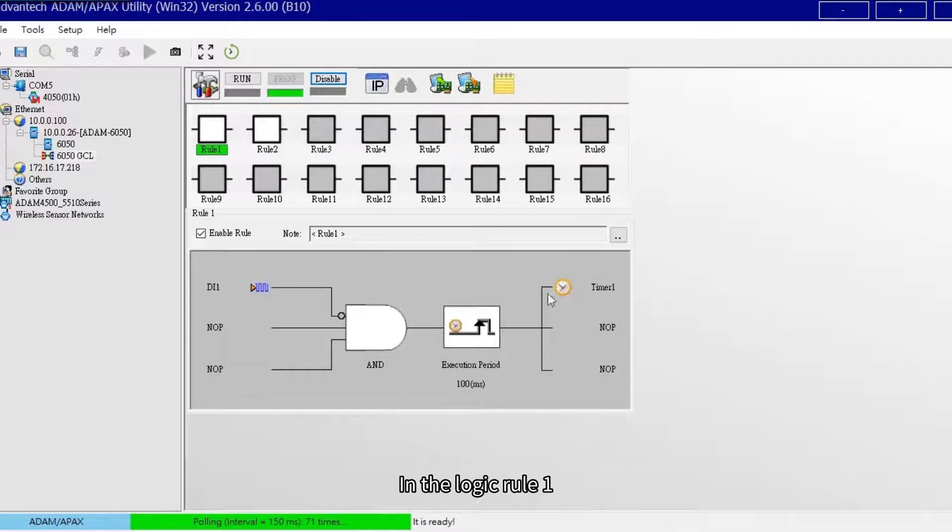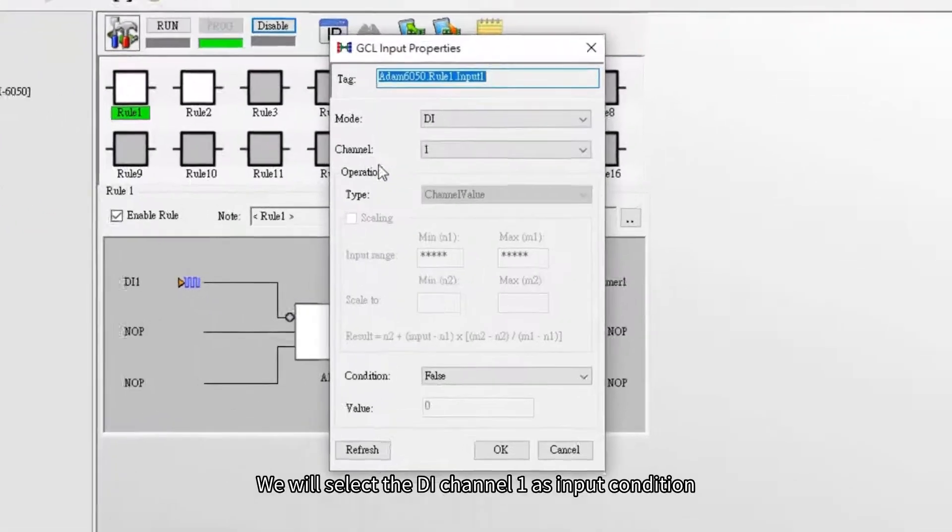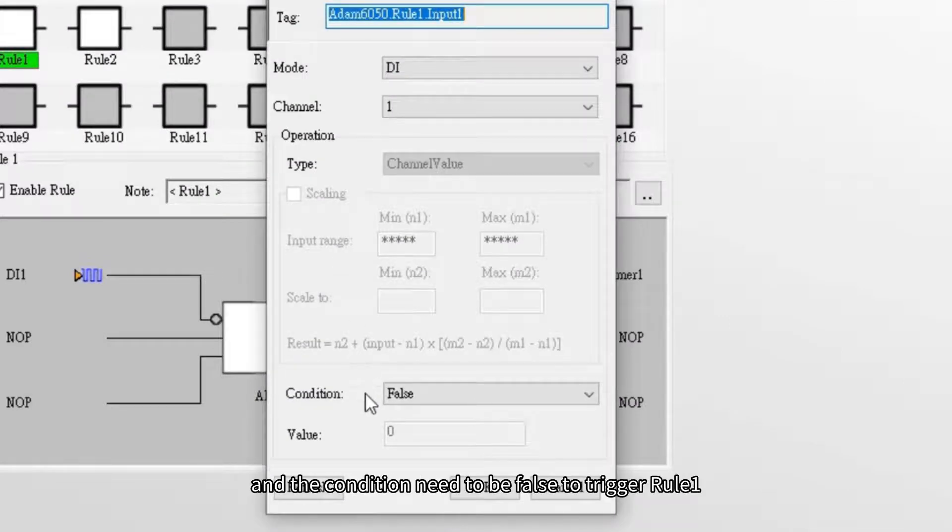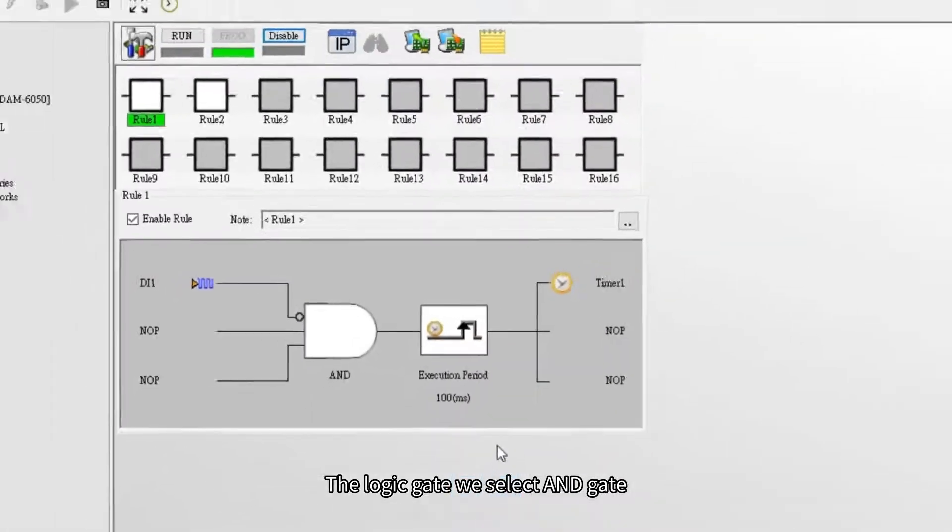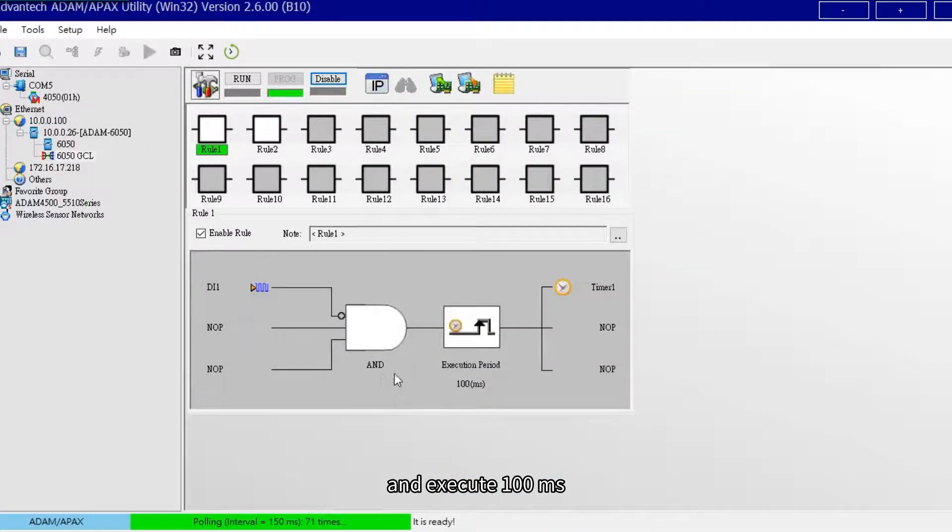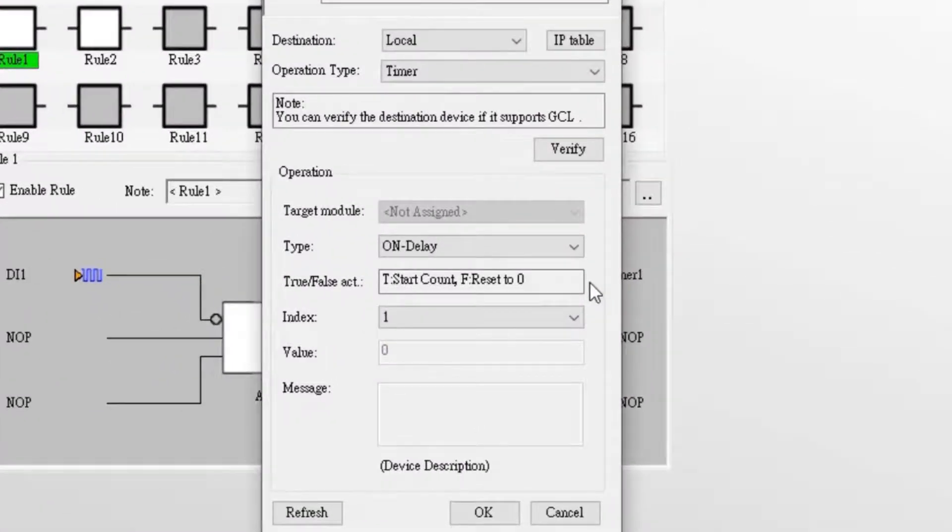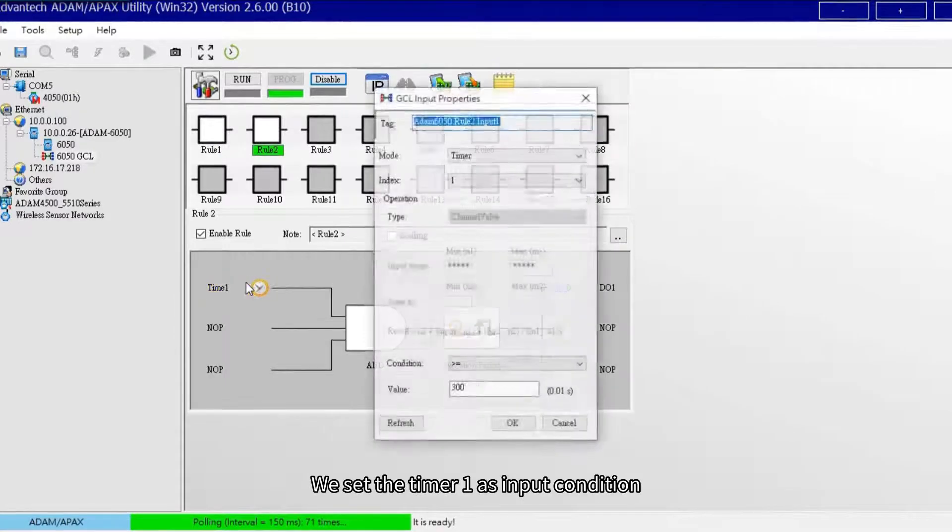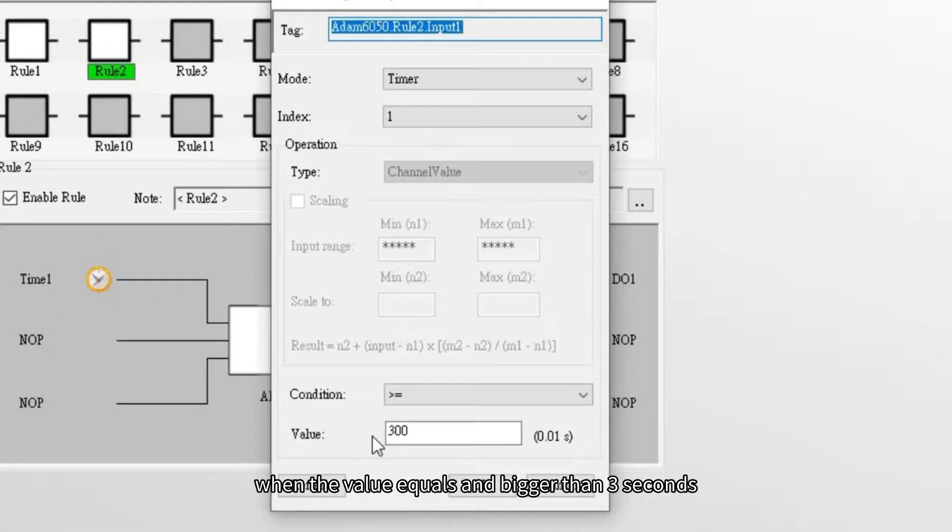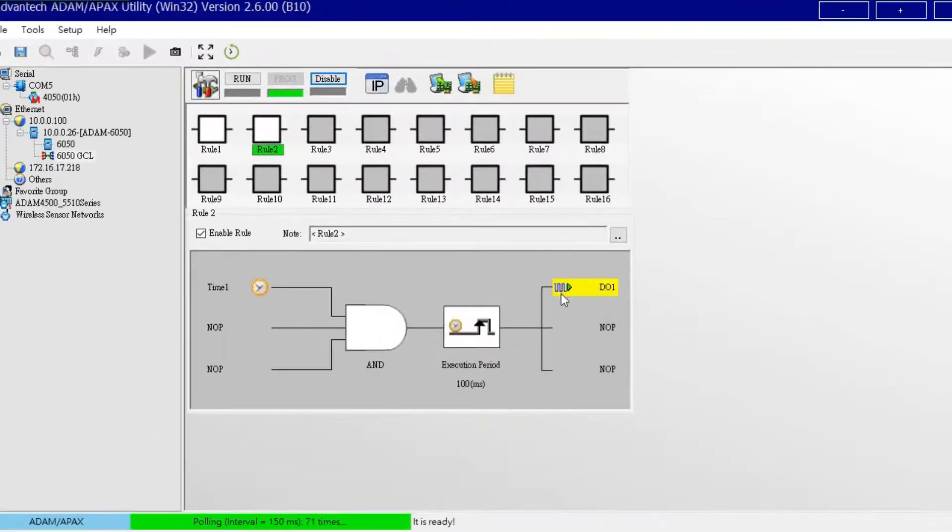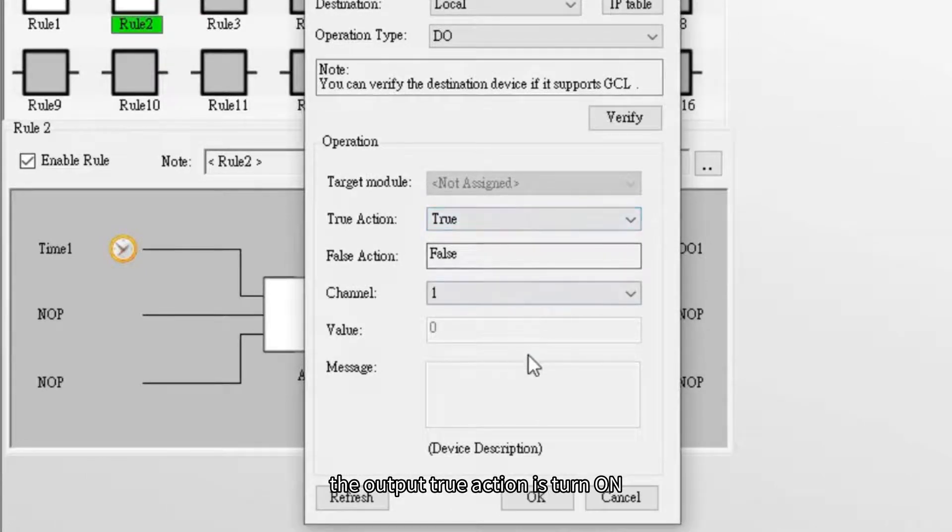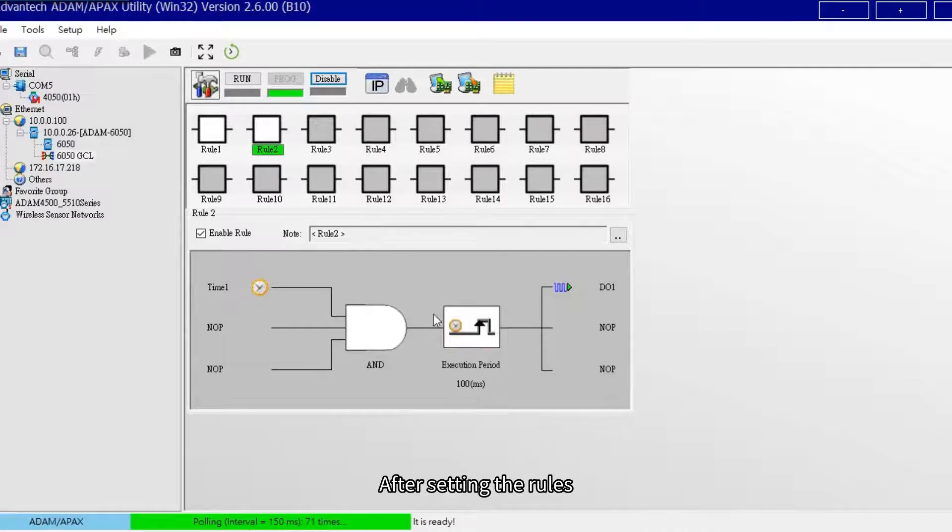In the logic rule 1, we will select the DI channel 1 as input condition, and the condition needs to be false to trigger rule 1. The logic gate, we select AND gate and execute 100 milliseconds, then trigger the timer 1 to do the on delay. In the logic rule 2, we set the timer 1 as input condition. After timer 1 starts counting, when the value equals and bigger than 3 seconds, it will trigger the DO1. The output true action is turned on when receiving logic true.